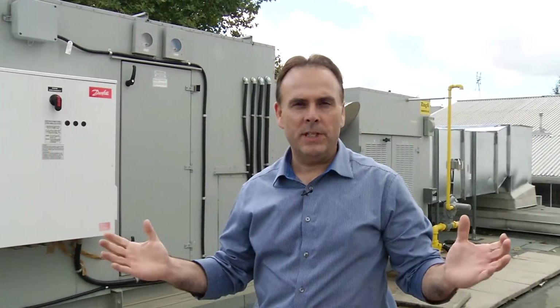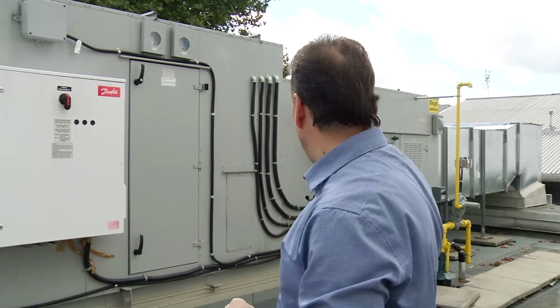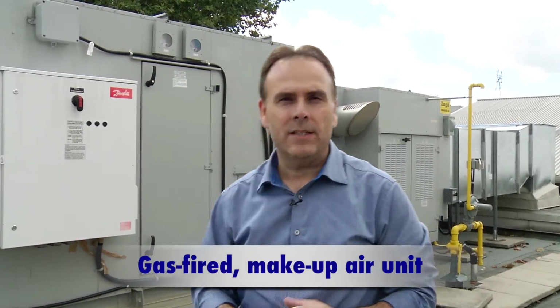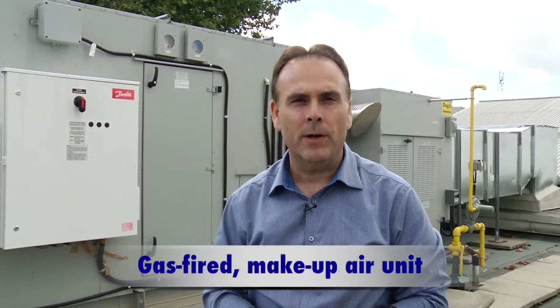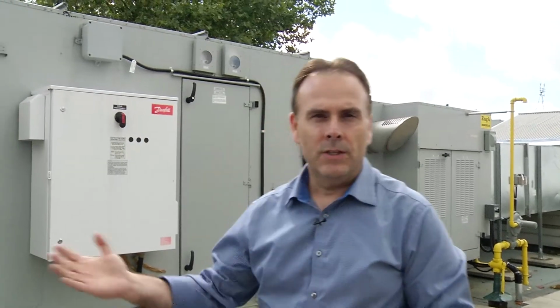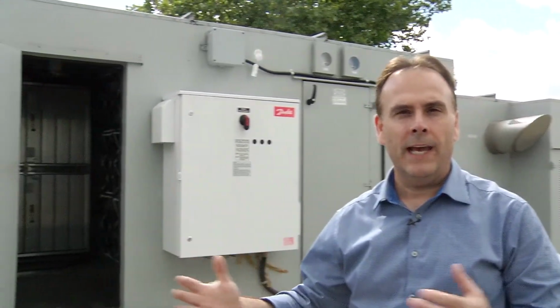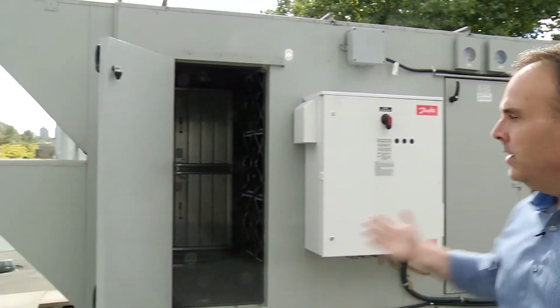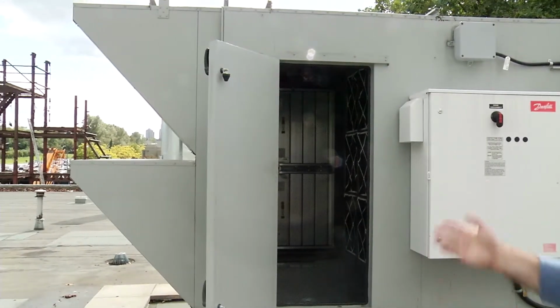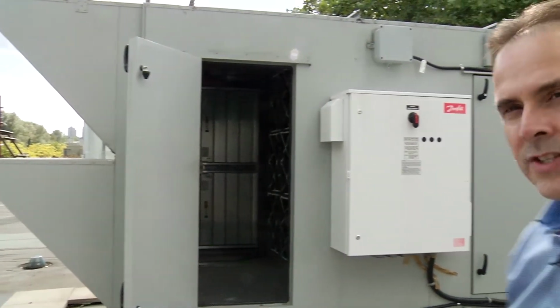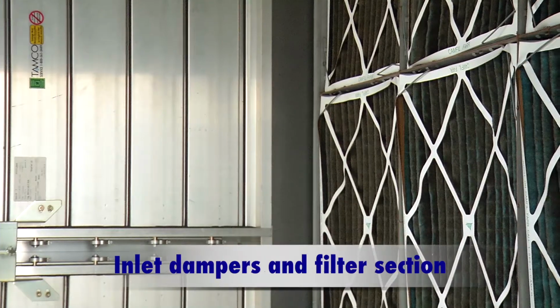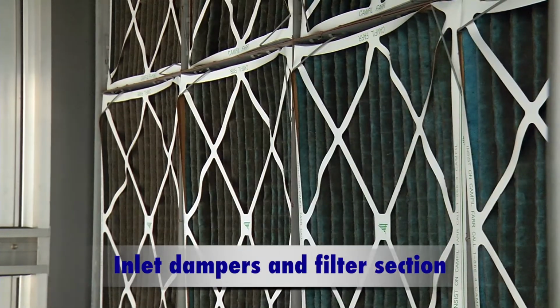Okay, the other piece of equipment up on the roof that we wanted to point out to you today is the gas-fired makeup air unit. It's a high-efficiency gas-fired makeup air unit that also has variable speed control on the fan that's synchronized to the exhaust system. So as the exhaust system that we've been looking at speeds up and down, so does the makeup air unit. I've got one of the doors open so that we can look inside to see the inlet dampers and filter section on the air handling unit.